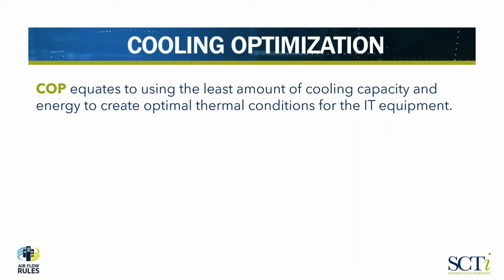So what's that mean? Well, first of all, we optimize airflow, which allows the least amount of cooling capacity to be used to meet the needs of the IT equipment. And by reducing operating cooling capacity, we reduce the cooling energy costs. Usually our results are a very substantial reduction in cooling costs. The primary objective though is to ensure that the IT equipment is operating in an optimal thermal environment and that operating costs have been reduced.